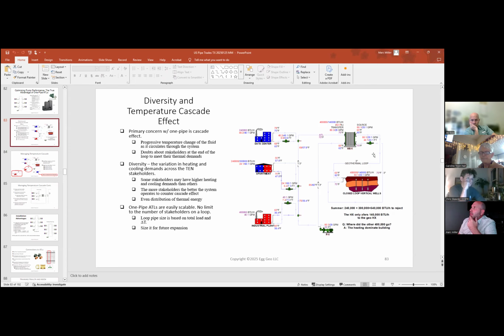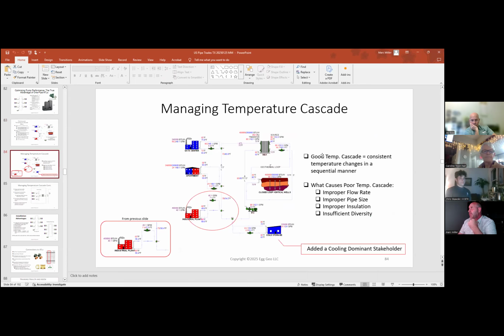Same with the pump that circulates water down to your geothermal loop, okay? They're variable frequency drives, meaning they vary their flow rate based on demand. And that demand is, it's looking at always maintaining this 10, 15, 20 degree delta T here that we have across the heat exchanger, okay? So it's not controlled by differential pressure, which is a traditional system, which looks at the differential pressure between the supply and return line, which then tells the control logic whether to speed up or slow down the pump, okay? Because in theory, if all your control valves open, then your DP goes to 0 and it tells the pump to speed up.